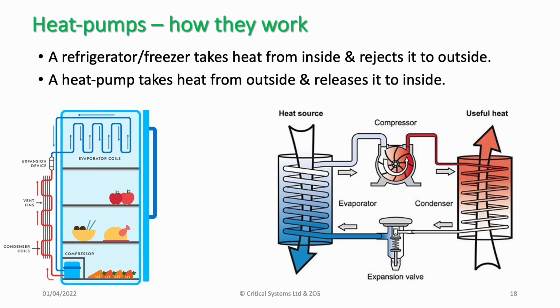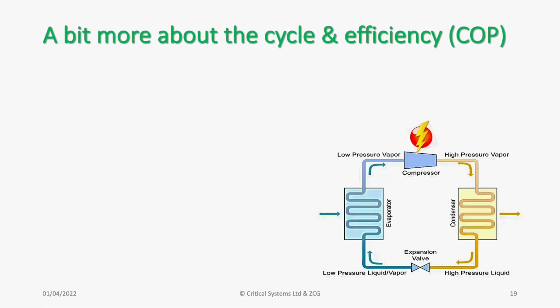So here it takes heat from outside, effectively cooling the outside air as its heat source, and it rejects that heat in the condenser inside our building into the heating system, whatever that may be. And in most cases, our domestic heating systems are waterborne, pipework distributing the heat in water to radiators or underfloor heating. So let's look a little bit more about the heat pump cycle and its efficiency. And its efficiency is described as coefficient of performance. And this is a very important term.